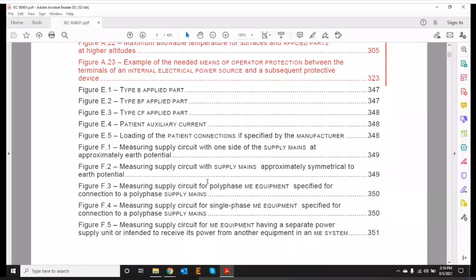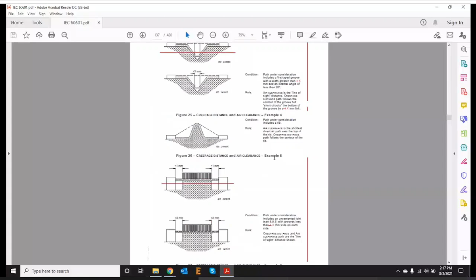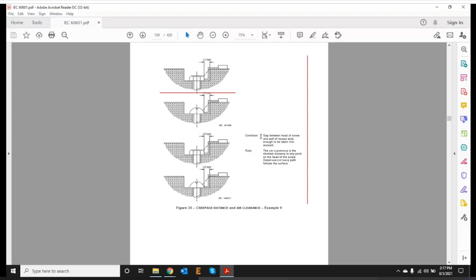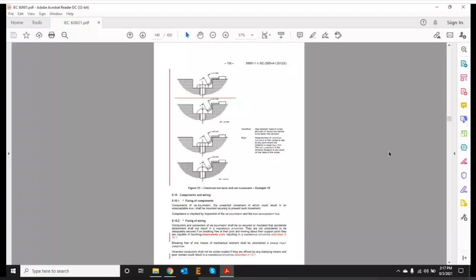here's the clearance and creepage part I was talking about earlier. The clearance distance, the creepage distance, the air clearance, the mechanical conditions, how the mechanicals should be. It also tells you the notations or the symbols you need to have on your device.